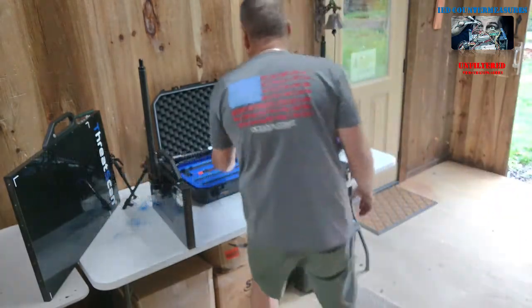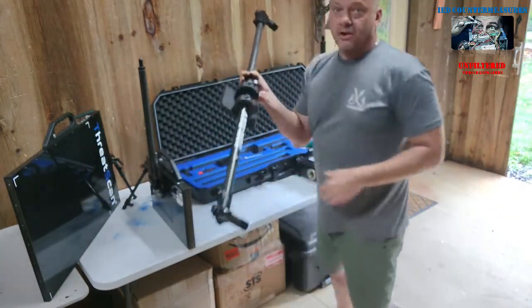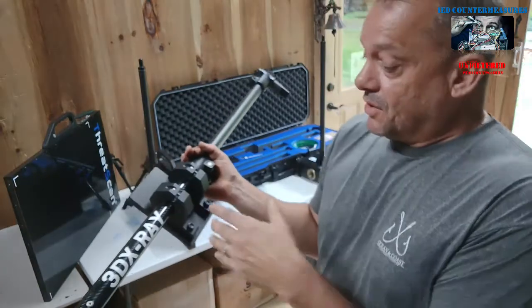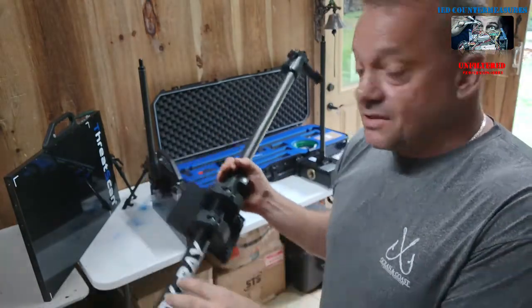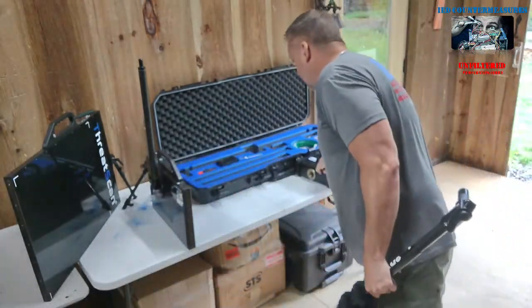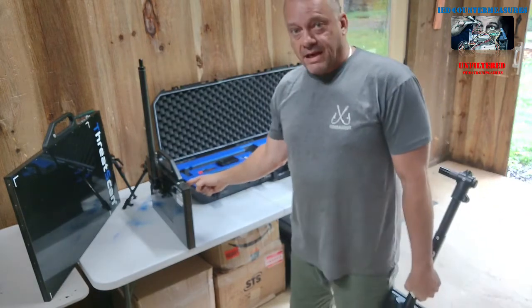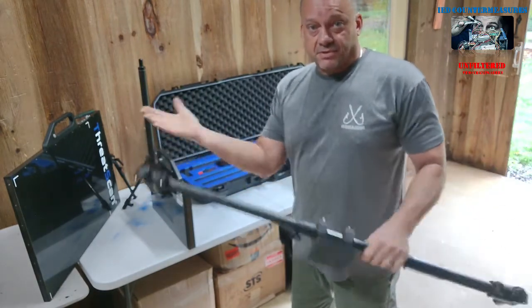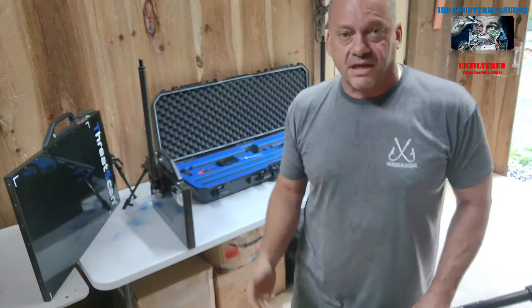Depending on which panel you're going to use, this C-arm is adjustable. The lowest distance is designed so you get complete X-ray beam coverage of your panel at the set distance, which on this one is about 90 centimeters.